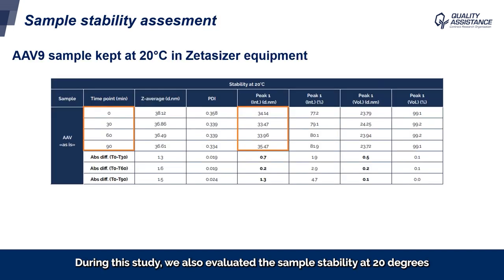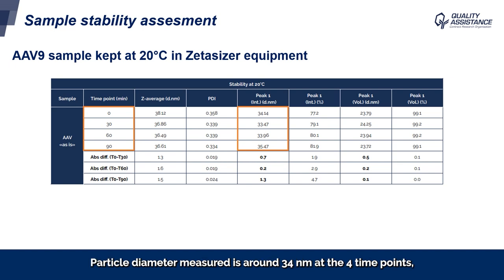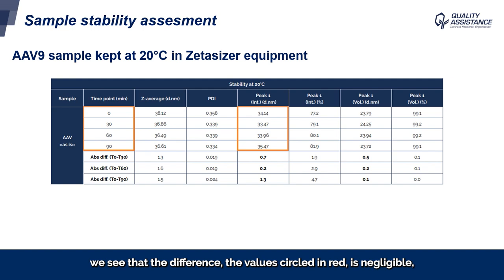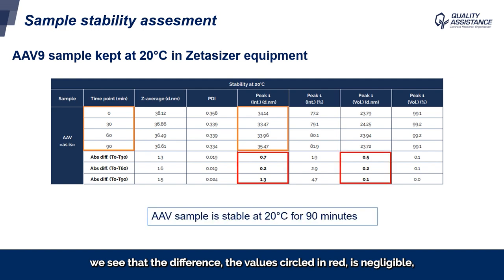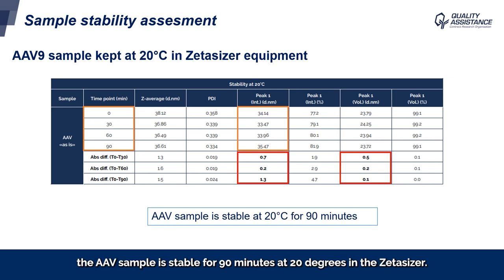During this study, we also evaluated the sample stability at 20°C by performing measurements at T0 and at three other time points: 30, 60, and 90 minutes. Particle diameter measured is around 34 nanometers at the four time points, circled in orange on the table. Looking at the difference measured between the different time points and time zero, the difference — the value circled in red — is negligible for the diameter, for measurements both by intensity and by volume. In conclusion, the AAV sample is stable for 90 minutes at 20°C in the Zetasizer.